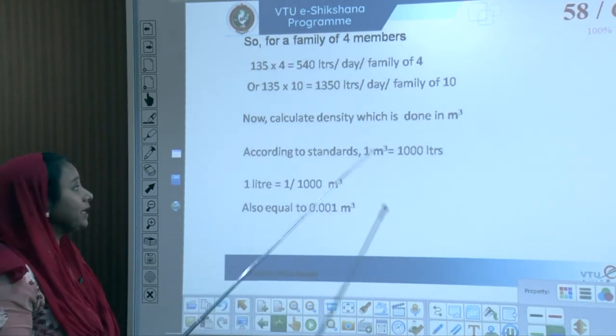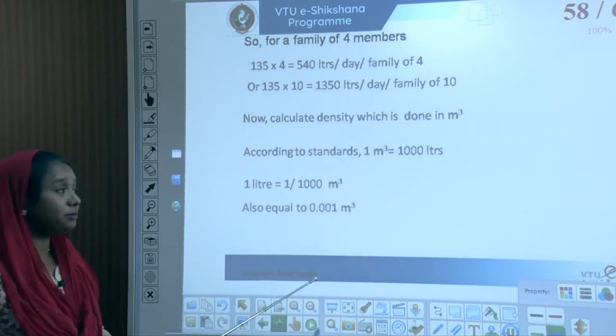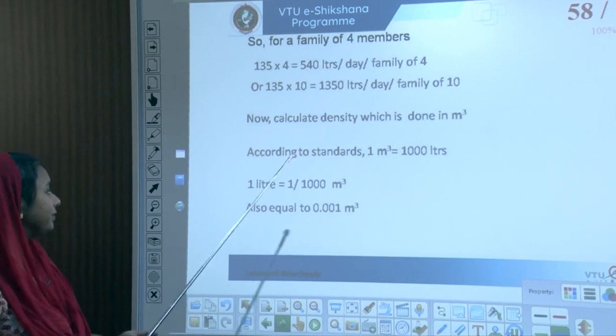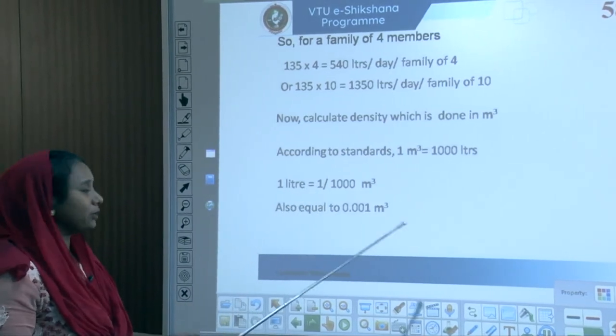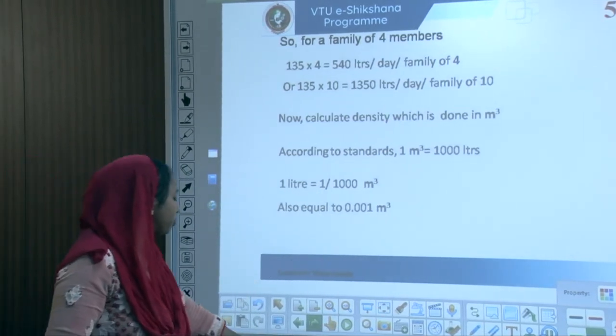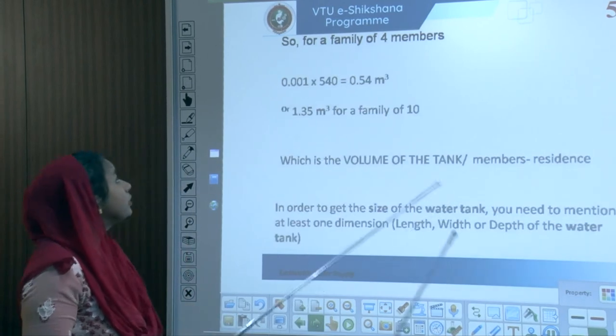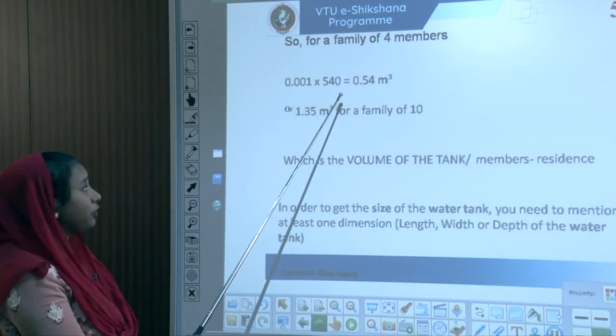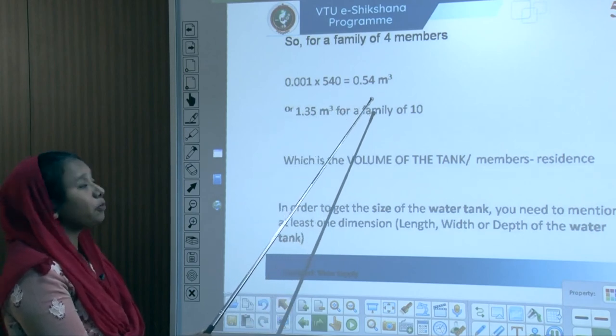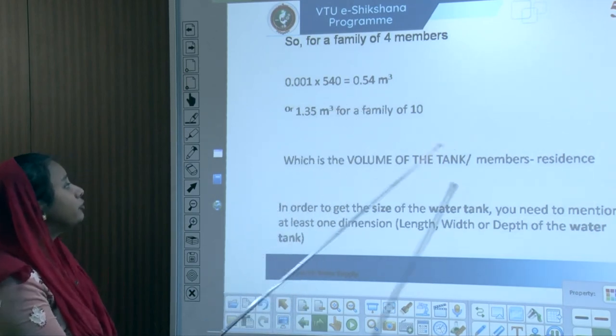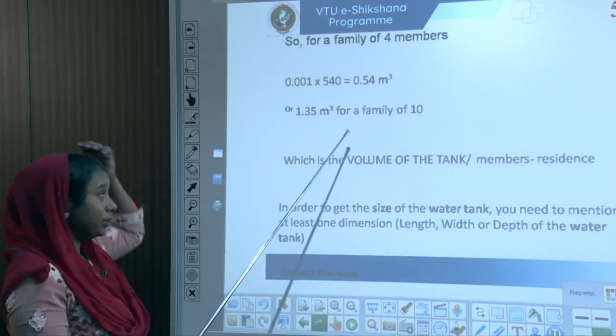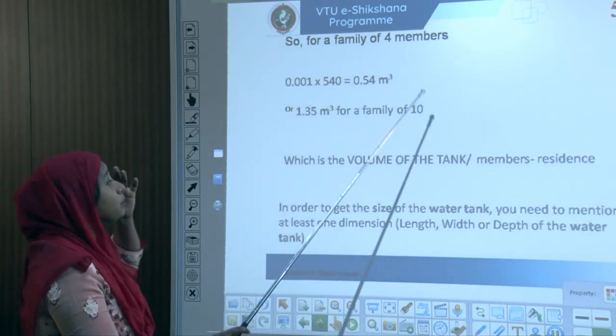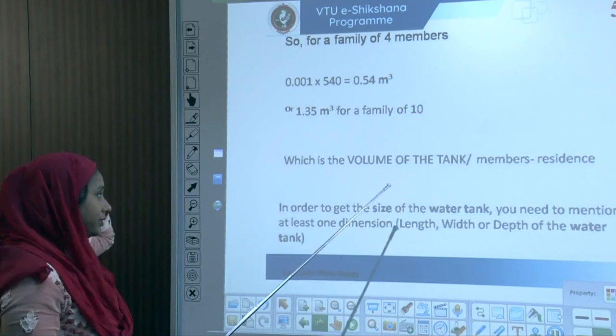To convert to cubic metres: 1 metre cube = 1,000 litres, so 1 litre = 0.001 m³. For a family of 4: 0.001 × 540 = 0.54 m³. For a family of 10: 0.001 × 1,350 = 1.35 m³. This gives the volume of the tank required per the number of residents.